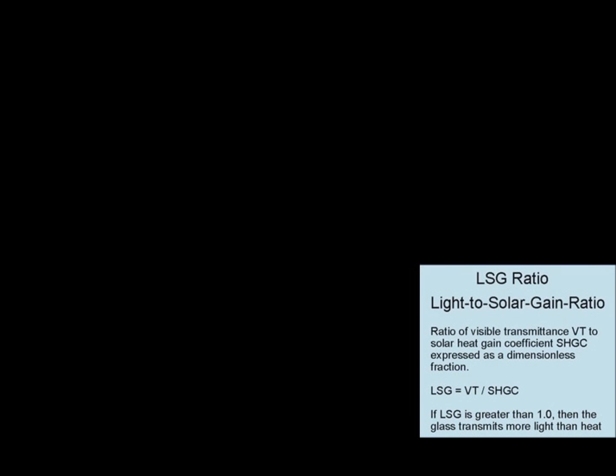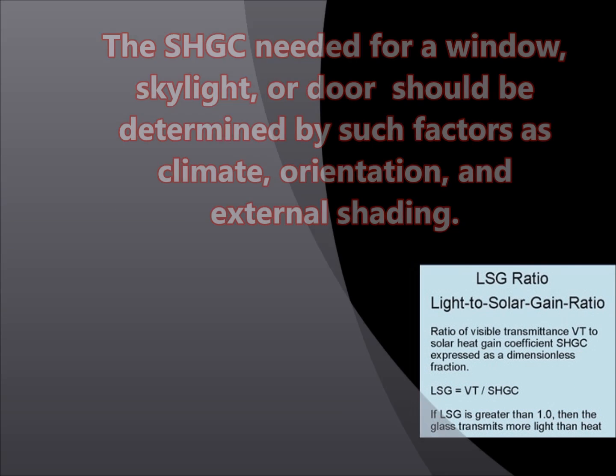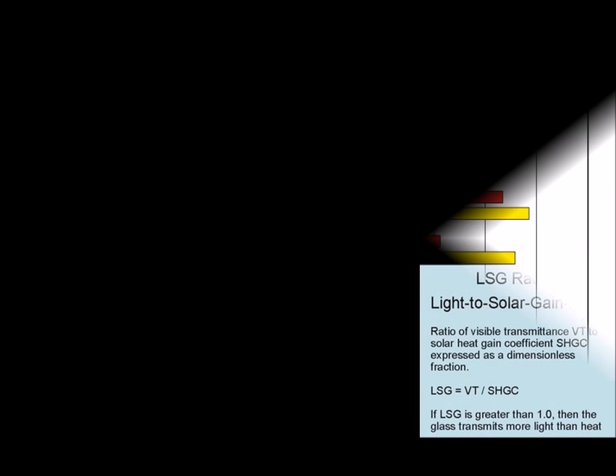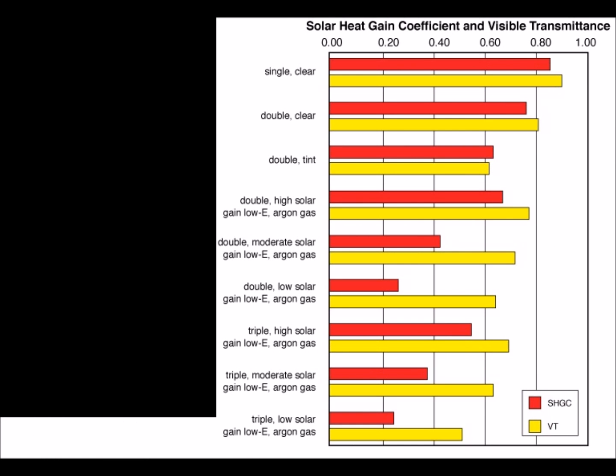A product with a low SHGC rating is more effective at reducing cooling loads during the summer by blocking heat gain from the sun. Therefore, the SHGC needed for a window, door, or skylight should be determined by such factors as climate, orientation, and external shading. Next we look at air leakage. The rate of air infiltration around a window, door, or skylight is in the presence of a specific pressure difference across it, expressed in units of cubic feet per minute per square foot of frame area. A product with a low air leakage rating is tighter than one with a high air leakage rating.